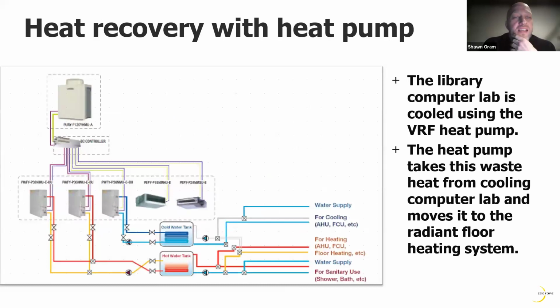One of the key innovations here was hooking up a computer lab inside of this building. It's the town's central computer lab. That was connected via refrigerant to the hot water producing heat pumps for the radiant floor. So essentially we get heat recovery off of the computer lab cooling, and we dump it into the radiant floor.